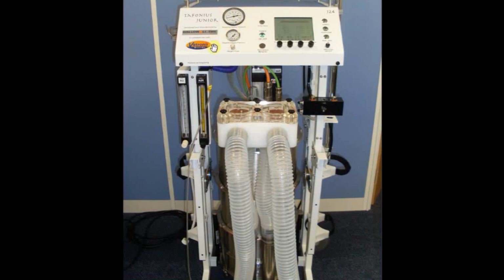Moving to the front of the machine at the top here, we have a typical manometer gauge to measure the airway pressure. Below that is the hospital oxygen gauge for incoming pressure from the hospital supply or from any e-cylinders, oxygen e-cylinders that may be fitted to the Junior. Below that is the white oxygen flush button, delivering 70 litres per minute when pressed, and that 70 litres a minute does not go through the vaporizer.